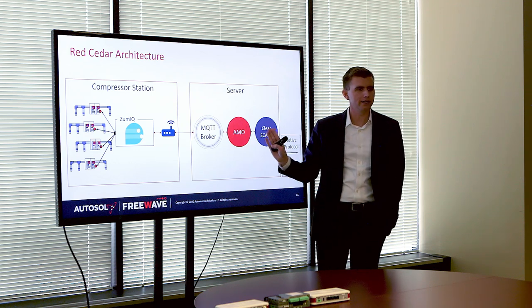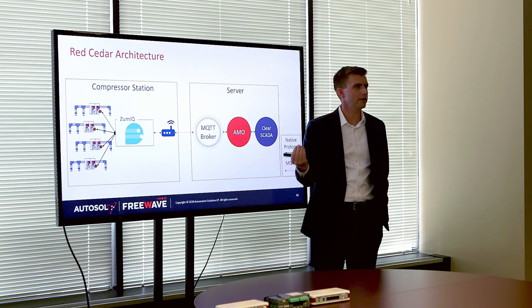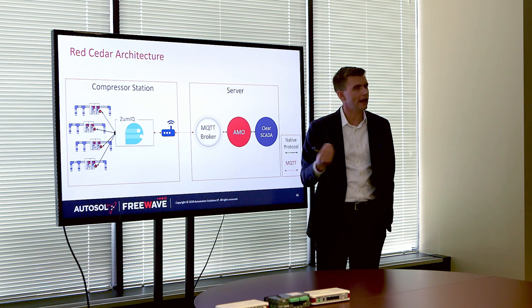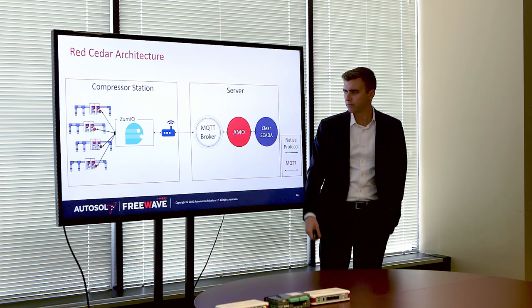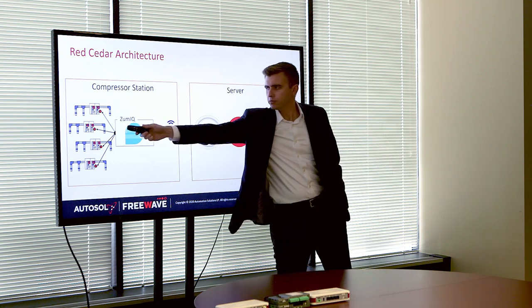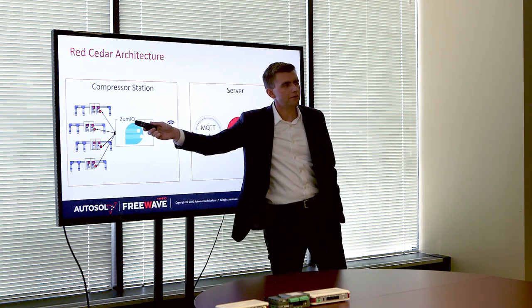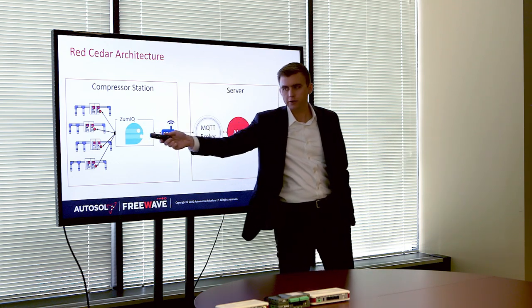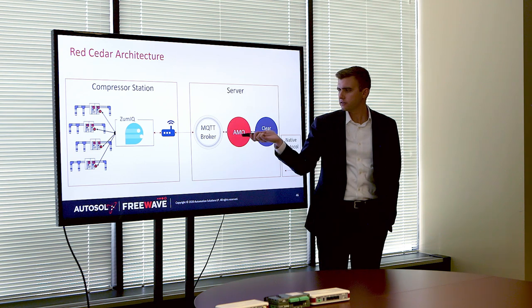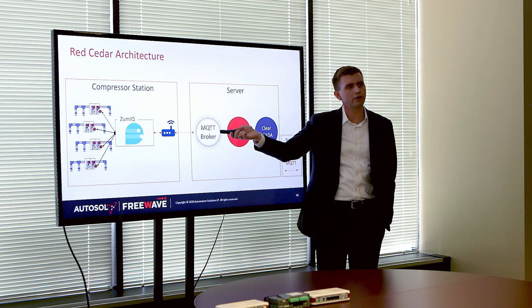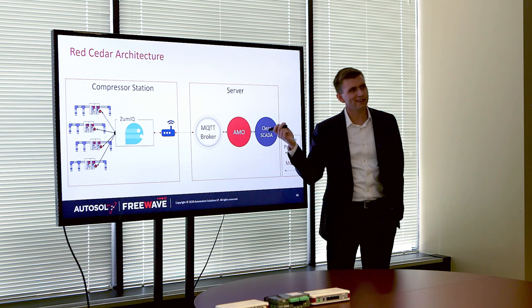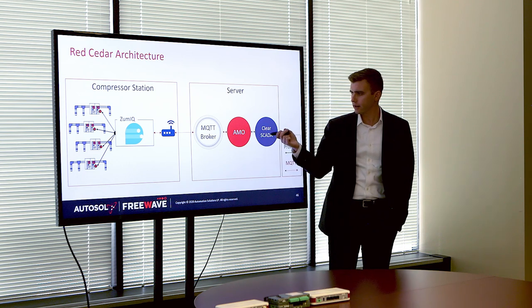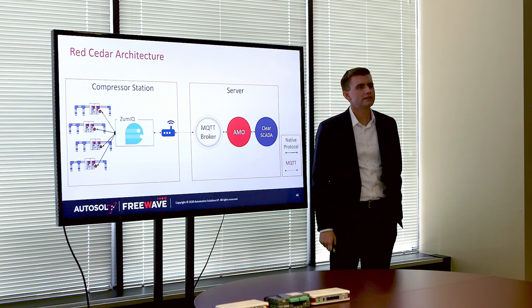Time was of the essence for them because they are getting fined $40,000 for every missing data incident. They wanted to get this out as soon as possible. So what we're doing is native protocol between Edge ACM and the device, MQTT to the broker. The Autosol MQTT to OPC converter takes everything off that broker and converts it to OPC DA, so an OPC DA client like ClearSCADA can then just get that data.